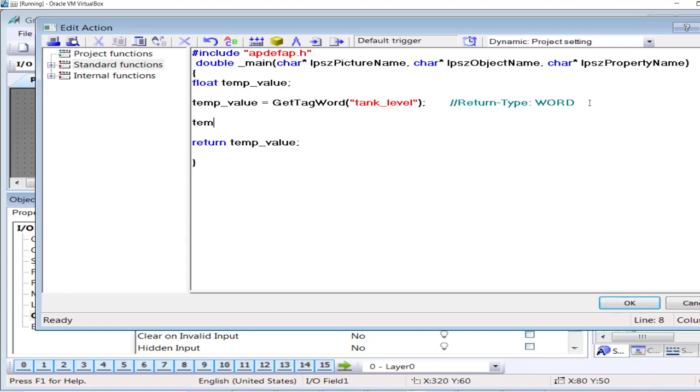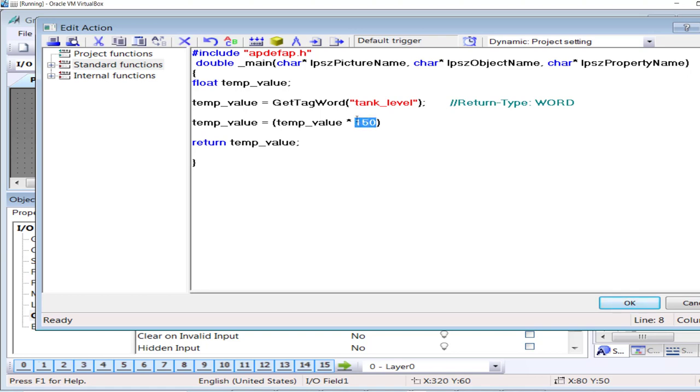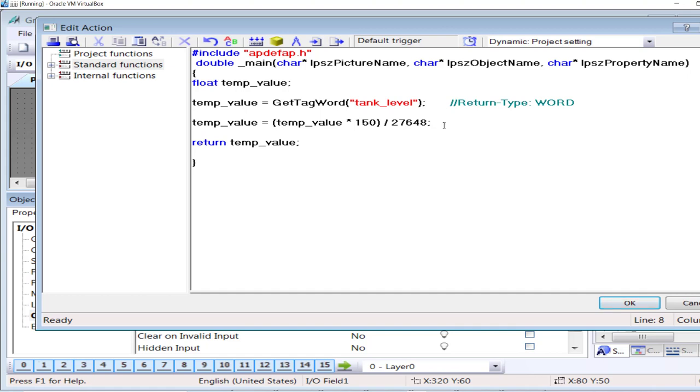My purpose is to convert it to the sensor range. For example, the range of the sensor is 0 to 150 meters. So I will make some calculations upon the received value from the function GetTagWord. Temp value: since the range of the sensor is 150, I will multiply it by 150. If you have a different range, for example 250 or 1000 or 500, you will enter that value here. And then I will divide it by this value, which is the range of the card channel: 27648.